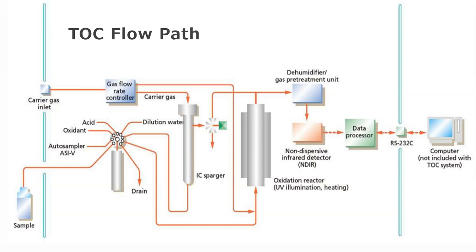Once our sample gets taken into this port, it's either sent to an IC sparger for measurement of inorganic carbon or our oxidation reactor for combustion. It's then dehumidified and scrubbed for halogens, and then sent to a non-dispersive infrared detector for detection. The software provided with the TOC can then process the data and it can be collected. We're going to briefly discuss each one of these components to help you understand what they do.